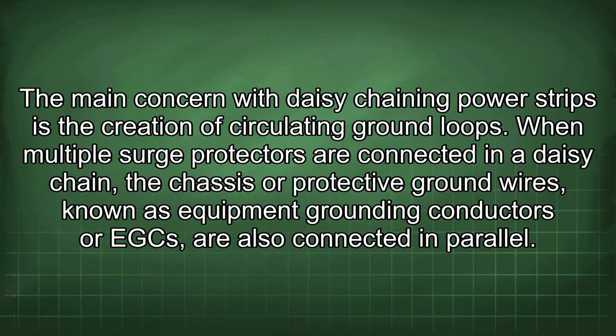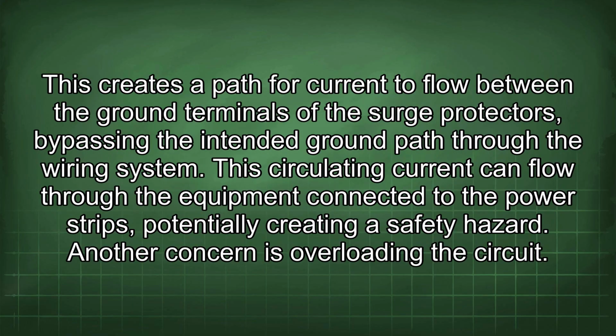The main concern with daisy chaining power strips is the creation of circulating ground loops. When multiple surge protectors are connected in a daisy chain, the chassis or protective ground wires, known as equipment grounding conductors or EGC, are also connected in parallel. This creates a path for current to flow between the ground terminals of the surge protectors, bypassing the intended ground path through the wiring system. This circulating current can flow through the equipment connected to the power strips, potentially creating a safety hazard.